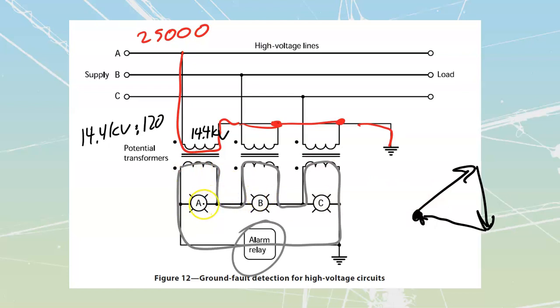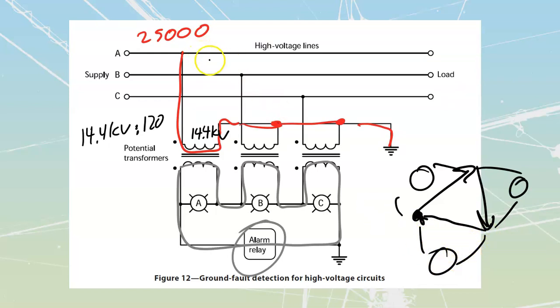Each of these lights is placed across the delta connected phases we have here. This light is connected in parallel, this one in parallel, and this one in parallel across there as well. So as long as each phase up top is good, each of these phases should also be good, and those lights should be lit.